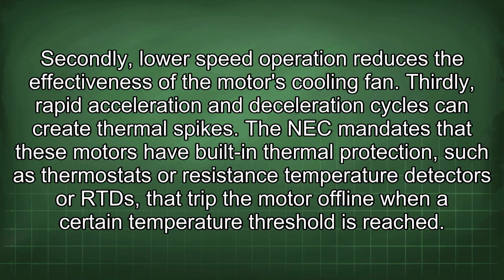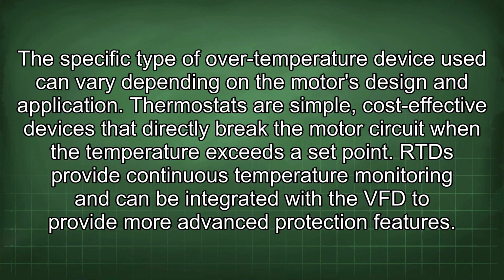The NEC mandates that these motors have built-in thermal protection, such as thermostats or resistance temperature detectors, or RTD, that trip the motor offline when a certain temperature threshold is reached. The specific type of over-temperature device used can vary depending on the motor's design and application. Thermostats are simple, cost-effective devices that directly break the motor circuit when the temperature exceeds a set point. RTDs provide continuous temperature monitoring and can be integrated with the VFD to provide more advanced protection features.